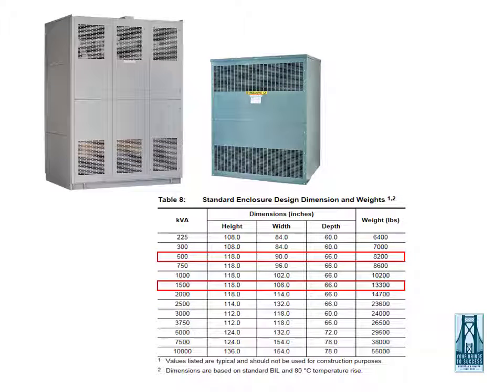In comparing the real estate of a 500 kVA and 1,500 kVA transformer, it has grown from 90 inches wide to 108 inches wide, but the height and depth remain the same size. Additionally, the weight has increased from 8,200 pounds to 13,300 pounds.